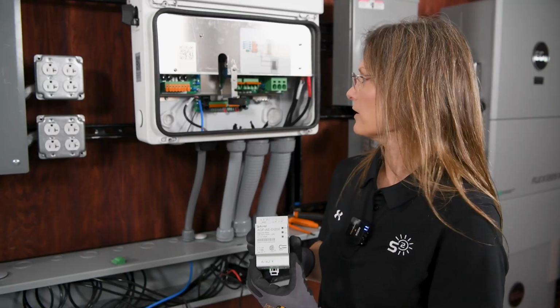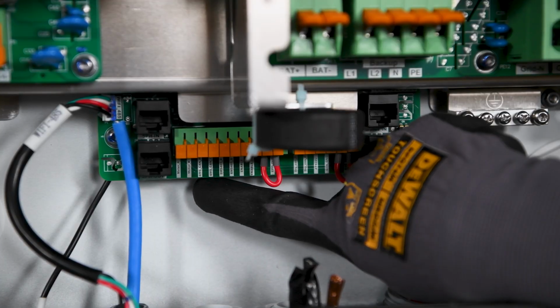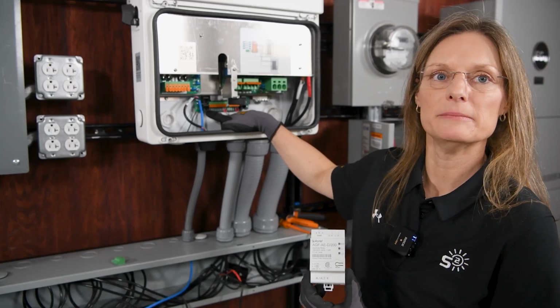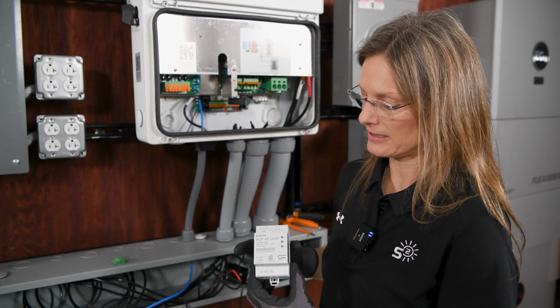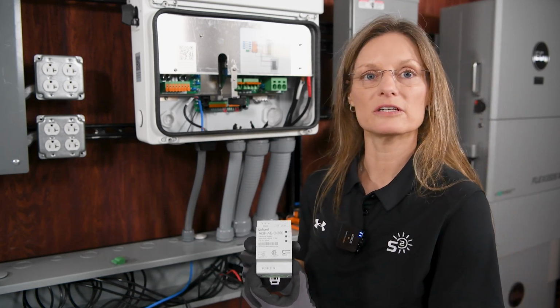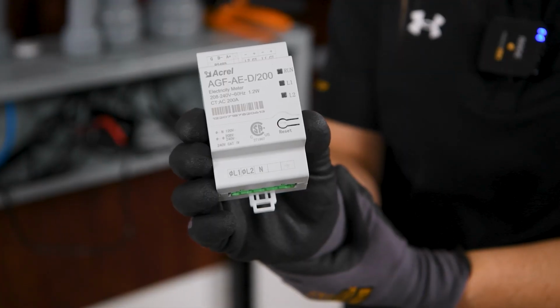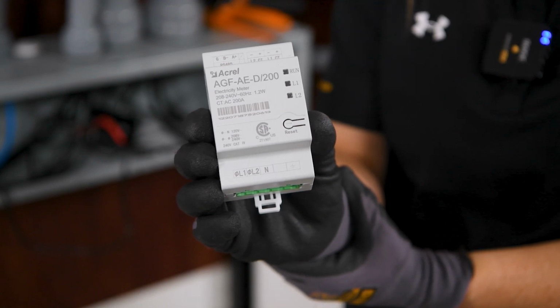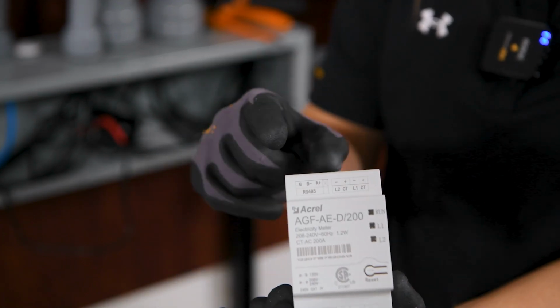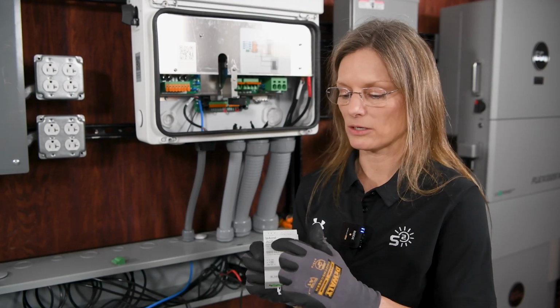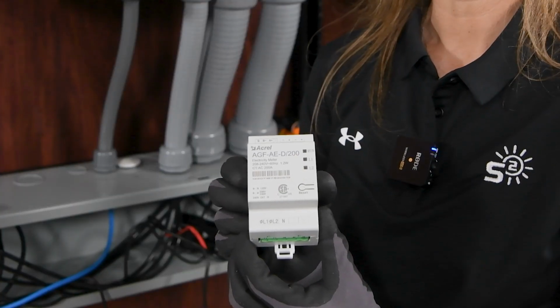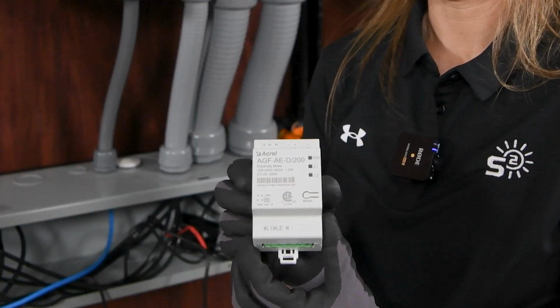So the first thing we'll wire up in our inverter are our communications. The first thing you see is the meter A and meter B inputs. That will be our communications with our electricity meter. For this one in our box, we have the Acrel meter. Some versions you may get may come with the Chint meter, which has a readout on that meter. They are all functionally the same and install the same way.